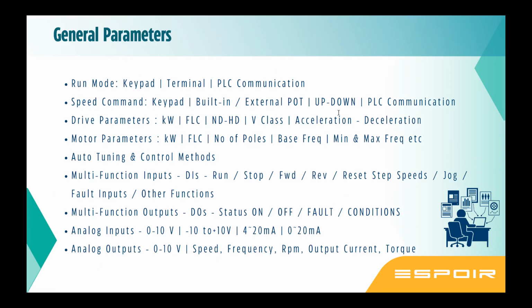Then comes an analog input. If we are going to run the speed through an external pot, you need an analog input. There is a source available within the drive, a 10-volt source is given to you. You can take that and give it as an analog input through a potentiometer to the analog input terminal, which is the point where you give the frequency command, the speed change command. It can be 0 to 10 volt, minus 10 to 10, 4 to 20 or 0 to 20. Where you have a distance issue, like a PLC or a DCS input, you use the current because there is no drop in the signal. If it is within the machine in a closed system, you can use voltage. For a longer system, you go for a current signal.